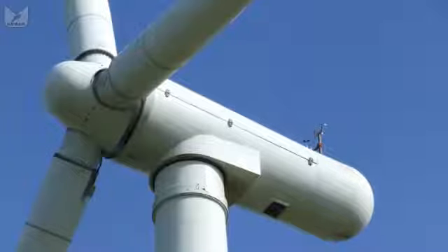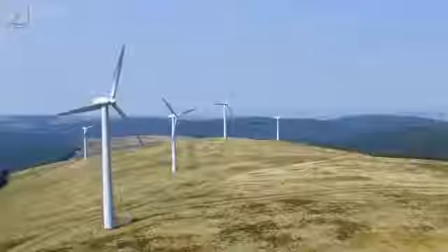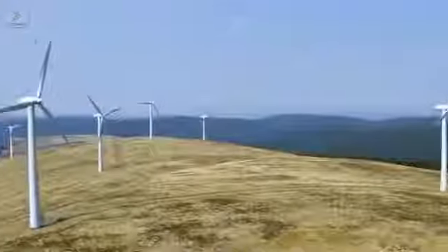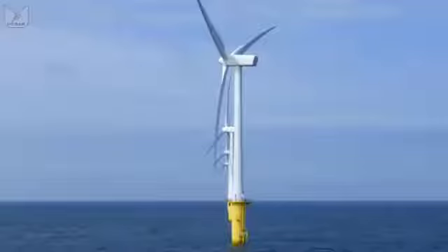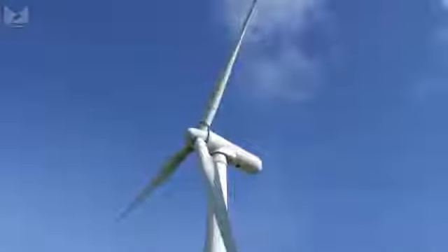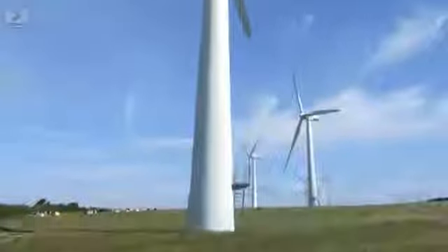And in this nacelle we have the generator, often a gearbox, and occasionally a high-voltage transformer, and the whole thing sits on top of a tower, which is mostly there to keep the blades from digging a hole. We tend to class turbines by their power output, and hence their physical size. Wind farms might use many sub-megawatt turbines, each producing 400, 600 kilowatts each, or a few multi-megawatt turbines, producing maybe up to 3 megawatts per unit. Apart from physical scale, they are arranged a bit differently, so let's start by looking at a typical sub-megawatt model.